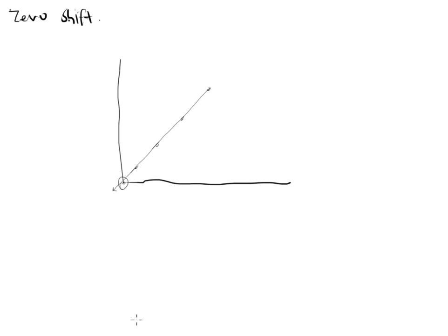If it goes through the point 0 or something close to it, then this is a prim and proper calibration curve, right? So we said that this is the purpose of the blank, and the blank is typically the solvent. And sometimes they call this word the matrix, all right? So it's typically the solvent, whatever your sample is being dissolved into, or whatever you're using to dilute your samples or your standards with, that is the solvent. That's what's being used as the blank. There's nothing else that should be present.